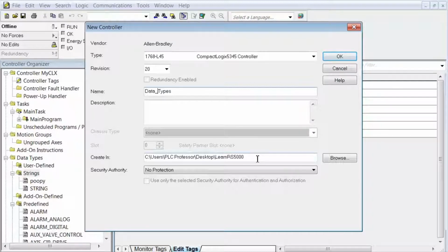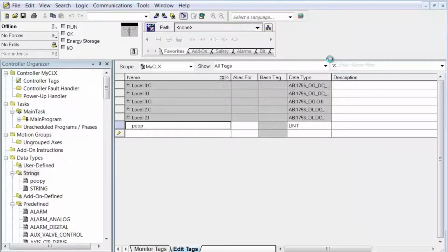We went through those specifically, and they make up all data structures in the Logix Engine. It is worthwhile to point out again that these data types are confined within the boundaries of a DINT or a 32-bit data type. Therefore, double integers are considered the native data type for the Logix Engine, and everything moves faster and more smoothly with DINTs, double integers. Our only interest in this lab project is to explore specifically what data types are available to the Logix Engine via RSLogix 5000. So we created a new project called data types, said OK.